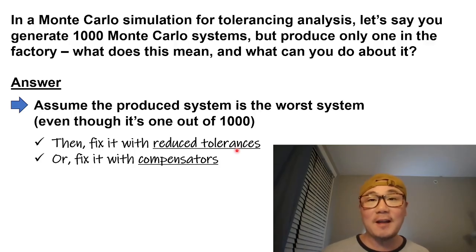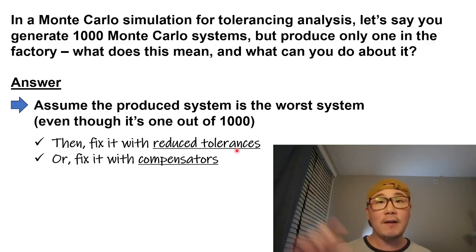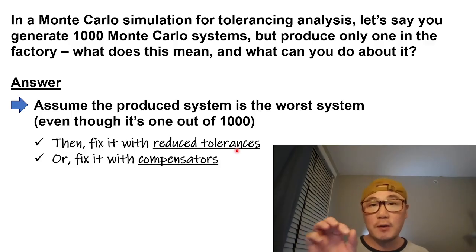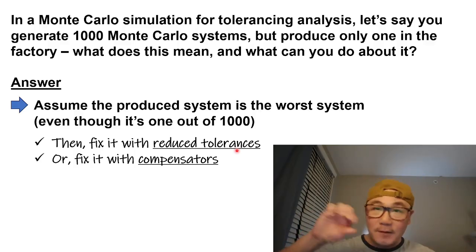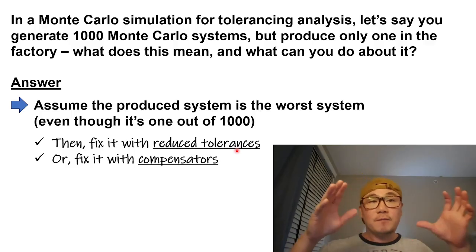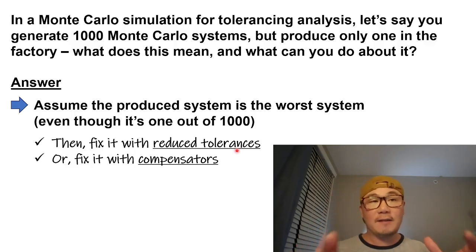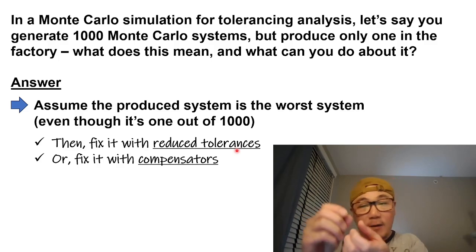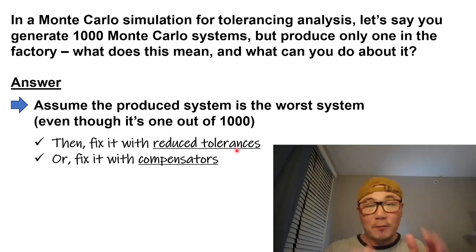So we are assuming here that every part that you take from your vendor is a Monte Carlo part. That means it's a randomly produced part under some distribution, and how you fit everything together is completely justified by some kind of random stochastic process that is repeatable. Every single day, your technician who comes in and puts a part in the instrument, he or she puts it in the same kind of way. It might be off this way or off that way in some random fashion, but it's always within this tolerance. But is that a good assumption?